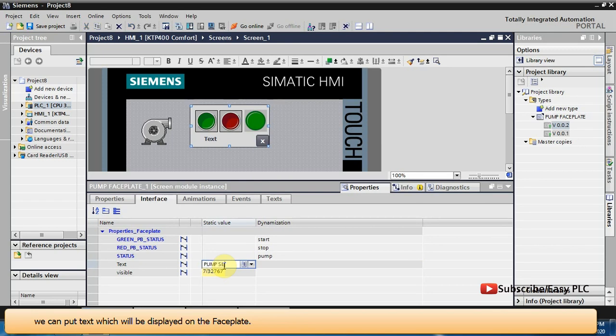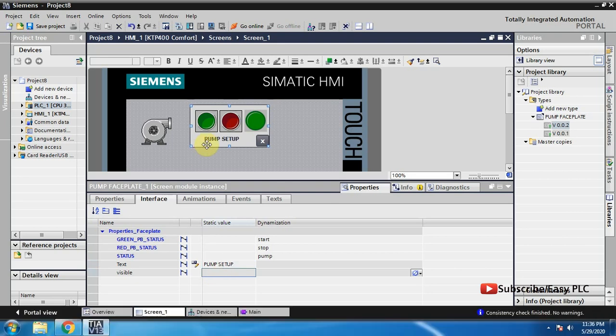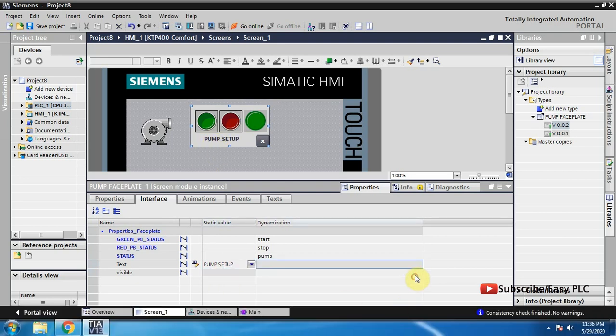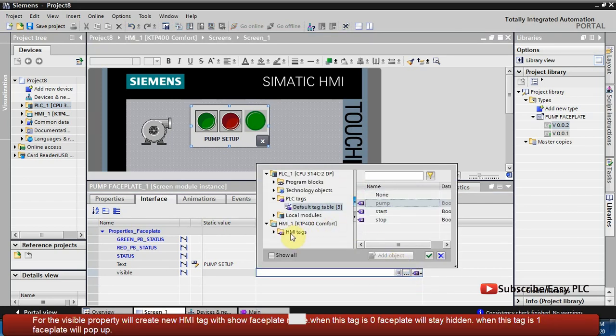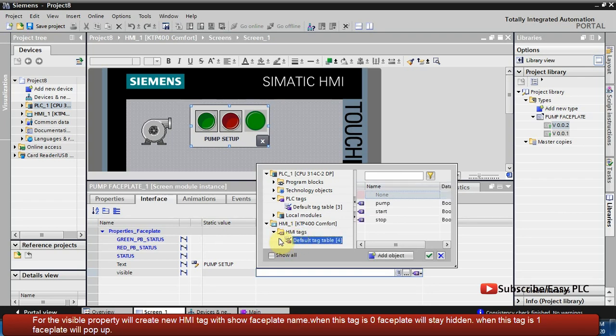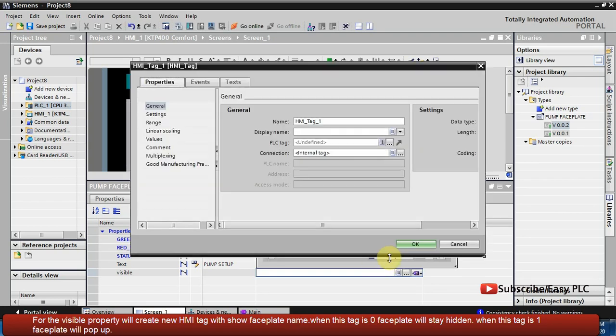We can put text which will be displayed on the faceplate. For the visible property we will create a new HMI tag named 'show faceplate'. When this tag is 0, the faceplate will stay hidden. When this tag is 1, the faceplate will pop up.